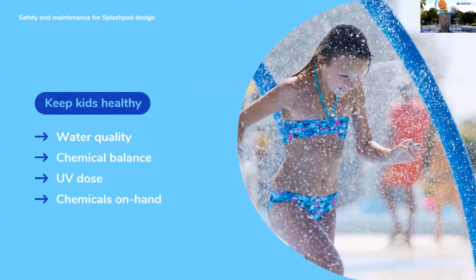Okay, so hopping back into our maintenance portion of the presentation. When it comes to keeping users healthy, we're essentially making sure our water quality is safe to play in. WQMS systems, water quality management systems, are designed to automatically sample water continuously and then adjust the chemical balance by adding chlorine or bromine or muriatic acid, or sometimes CO2. Further down in this presentation, we'll touch on how our systems can adjust to whatever you're comfortable with from a chemical standpoint.